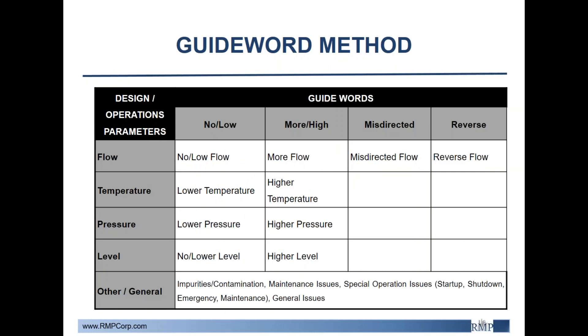In order to address these hazards, a systematic approach called the guide word technique is often used. This is accomplished by using words such as no, low, more, and high, and applying them to design parameters such as flow, temperature, pressure, and level. Combining these creates the deviation you can use to define your causes. For example, a low flow deviation can be caused by a valve being inadvertently closed.